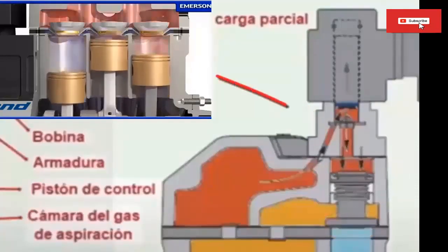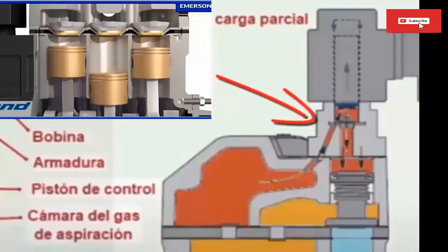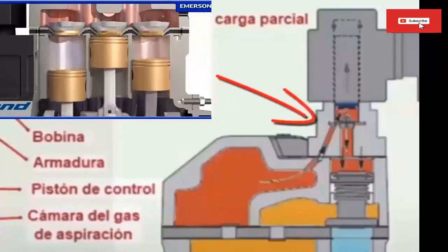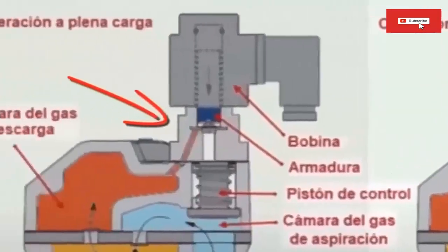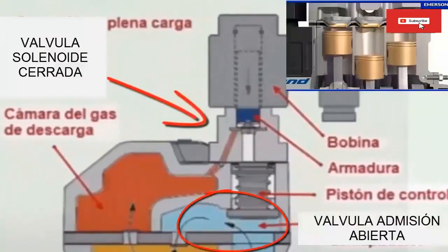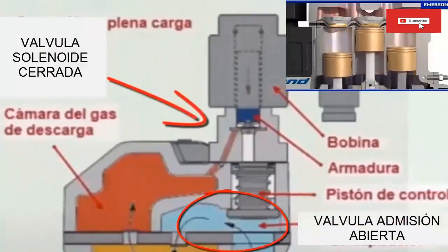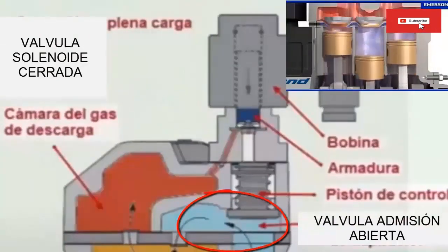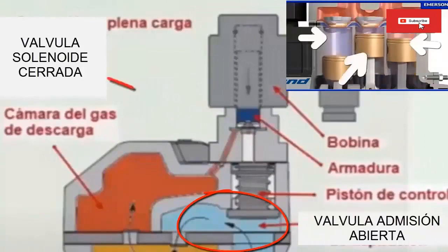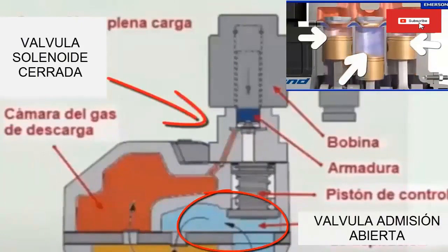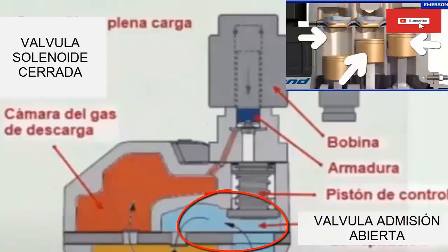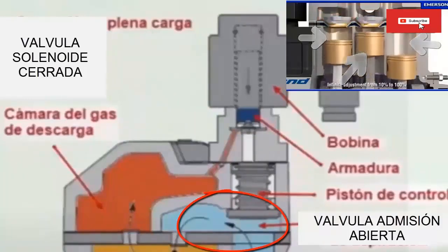10. In response to an increasing load, the controller sends a signal to close the solenoid valve. This closes the port, not allowing the pressurized refrigerant vapor to pass to the top. In this way, the intake of refrigerant gas is opened. 11. A controlled leak rate around the discharge valve relieves pressure, allowing the valve to open and refrigerant to once again flow into the cylinder to be compressed.